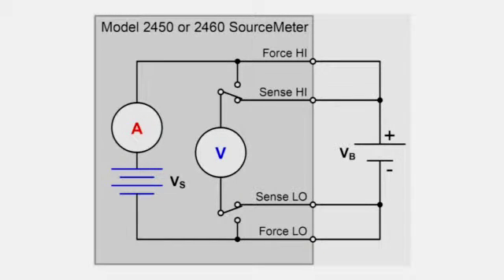So when it comes to these batteries and our source meters, we often have to get into different wiring configurations. A lot of people don't understand remote sensing, for example, when the currents get large or the lead resistances get long. So we build those capabilities into our products. We have a relatively sizable group of applications engineers around the world that help our customers understand all these subtleties and pick the right instruments for the job and then tailor those in how they're used.